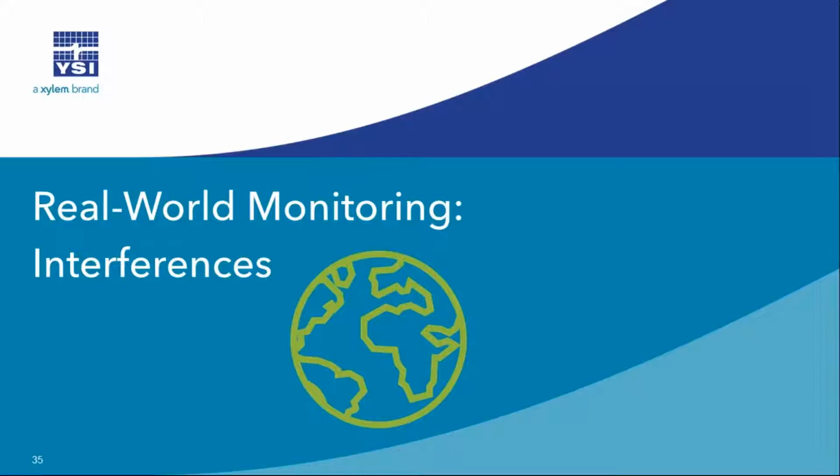and see if that 0 point is still sticking at 0. That is the 1 point that you can kind of come back to. But if you're getting drift on that other end of the curve, you might not know it. So Dan, it's a sound practice that a lot of people use. Just be aware of the risks when you take that route.